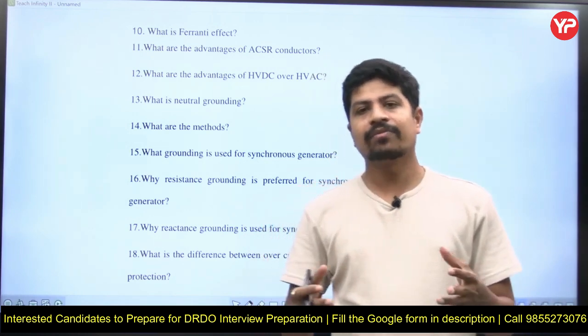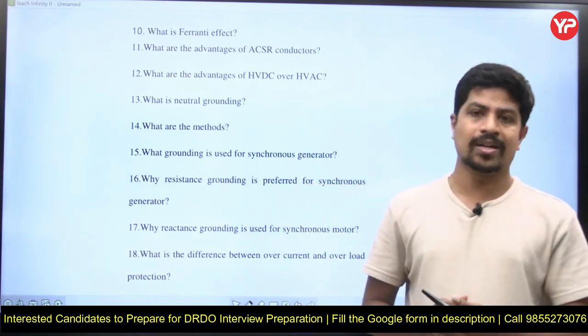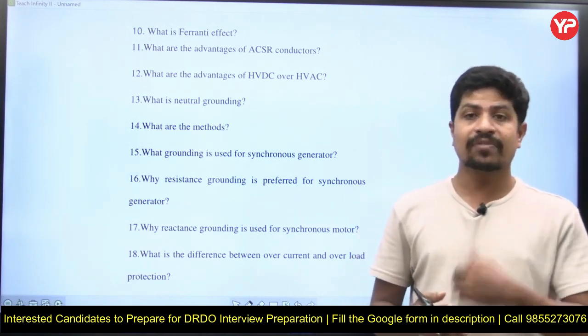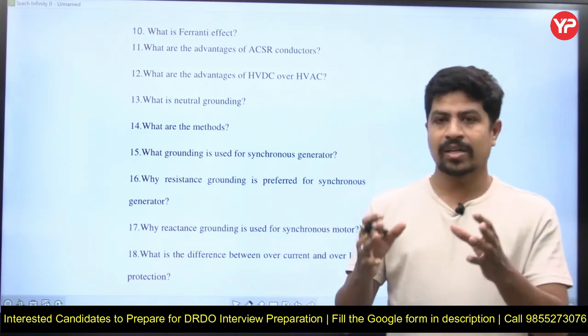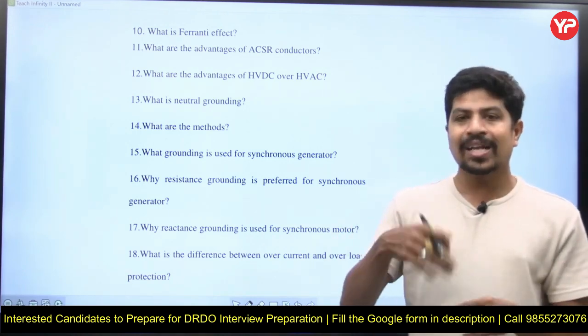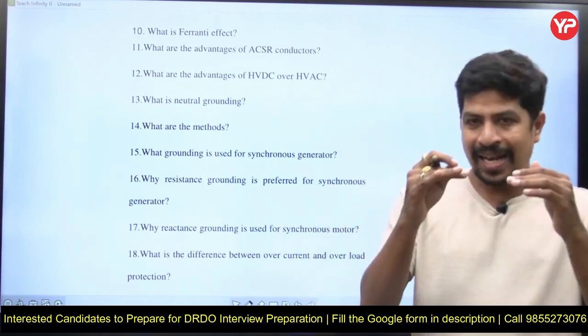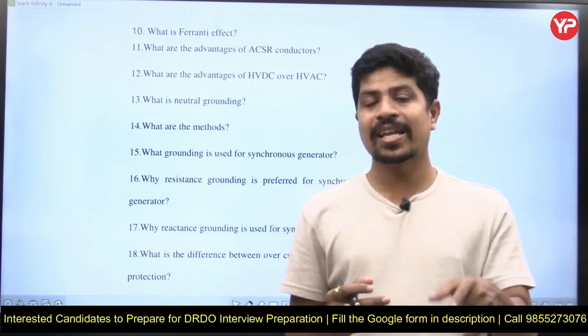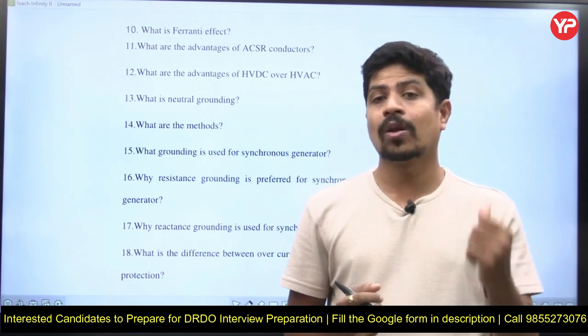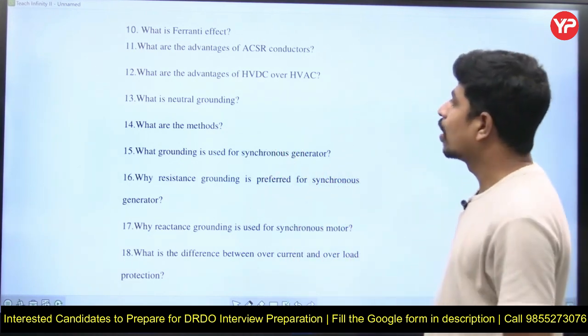What are the advantages of ACSR conductors? ACSR stands for Aluminum Conductor Steel Reinforced. Skin effect is less compared to a solid conductor, and transportation is easier compared to solid conductors. In a solid conductor, skin effect is high, so we use stranded conductors; but stranded conductors have low mechanical strength. Therefore, the inner aluminum strands are replaced with steel to improve mechanical strength. ACSR has less skin effect than solid conductors and more mechanical strength than all-aluminum stranded conductors.